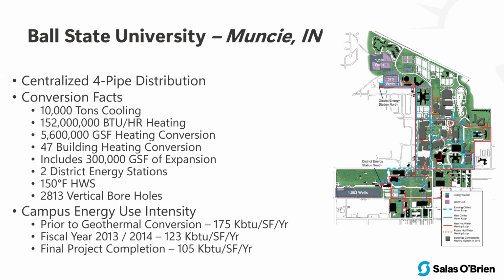One thing I just want to point out and get clear with this audience: I hear a lot about simultaneous heating and cooling, and I hear that term being used incorrectly. With a 5G system, when you have multiple buildings and heat pumps, that is not simultaneous heating and cooling. That's load sharing, or thermal energy sharing. Simultaneous traditionally means one device, one lift doing 2 jobs, meaning a chiller that's providing hot water and cold water at the exact same moment. That's simultaneous heating and cooling, and that's only done with a central plant. Now, you could have a 5G with central plants in each building providing simultaneous heating and cooling for that building, but to load share or have simultaneous operation on a network, if it's not a central plant, that's not possible. You're going to have one compressor doing cooling and one compressor doing heating. That's not simultaneous, that's just sharing energy back and forth because you're still doing 2 lifts, 2 jobs. So I just want to clear that up, make sure everybody understands that.